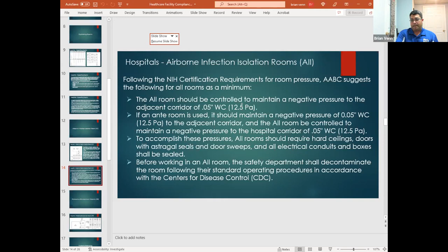Airborne infectious isolation rooms should require hard ceilings. I've seen them not be installed, or a room repurposed. It definitely is not a good idea to have drop ceilings. And then you also need to have doors with sweeps and seals. Obviously the door is where we're looking for that pressure, and sometimes if we don't have proper seals at the base of the door or under the door, then we won't be able to achieve that pressure.